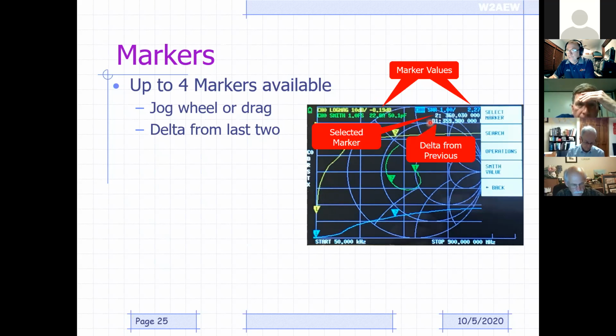The delta, the D1, when you bring up a second marker, it's going to give you the delta from that marker you just brought up, the active marker, in this case 2, with respect to the previous marker that you selected, which in this case was 1. So now I've got an active marker of 2 and the delta of 2 to 1. So if I want to measure some parameter between two markers, like the ratio of gain from this frequency to that frequency, you'd bring up those two markers and the delta would give you that. Okay.